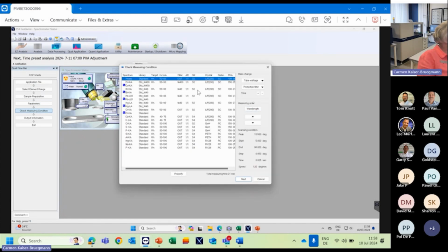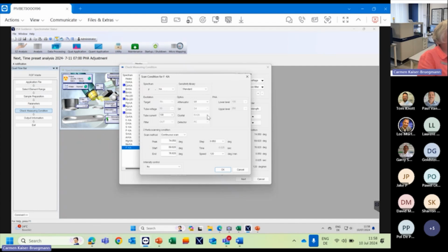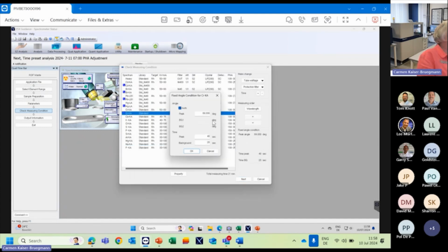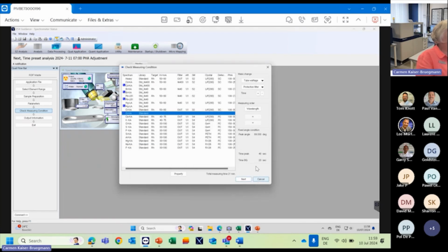These are the instrumental conditions that will be used and defined, so you don't have to think about what you want to do. It already makes the method for you. However, if you have a lot of experience and you would like to look at a certain element with a longer measurement time, you can go into each condition and change the settings. So you can go continuous or step scans, for example. Under fixed angles, you can define peak and background measurements.